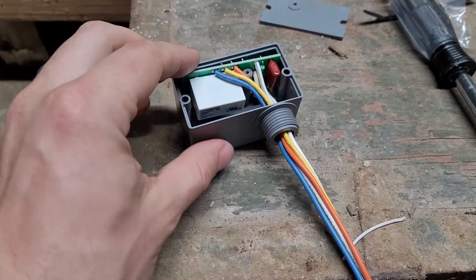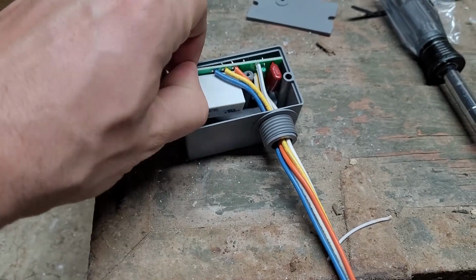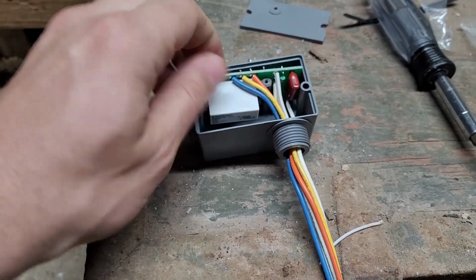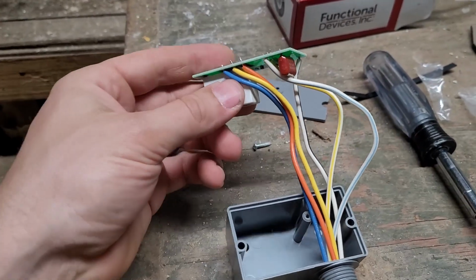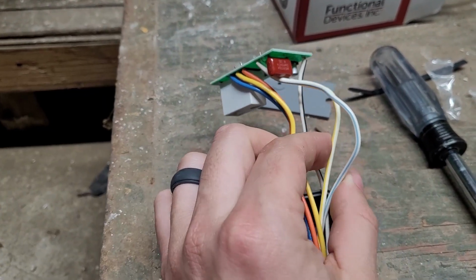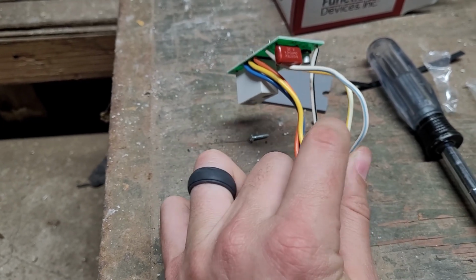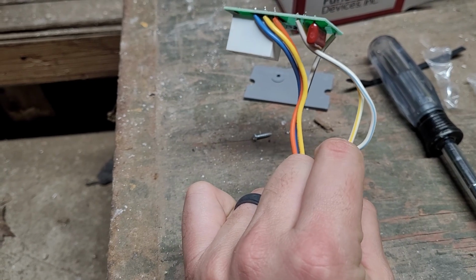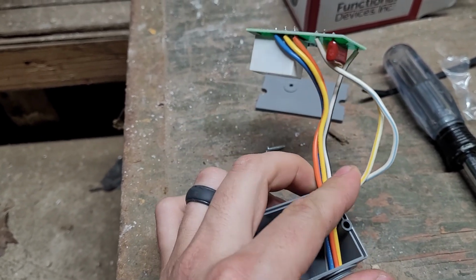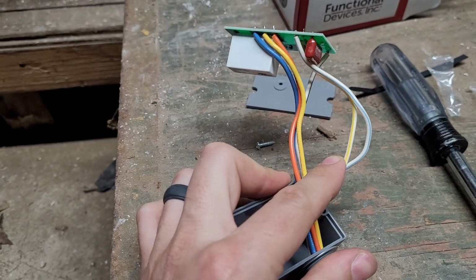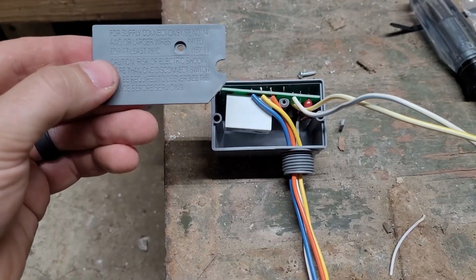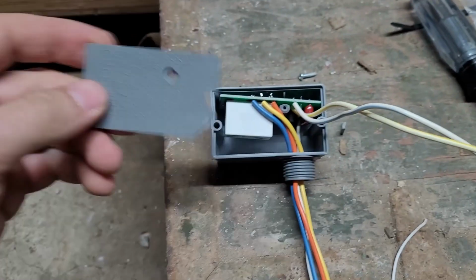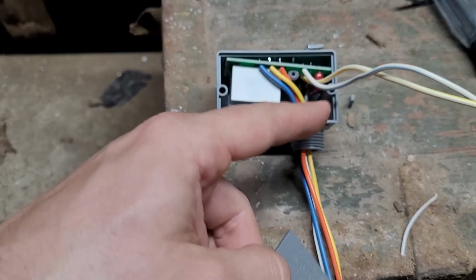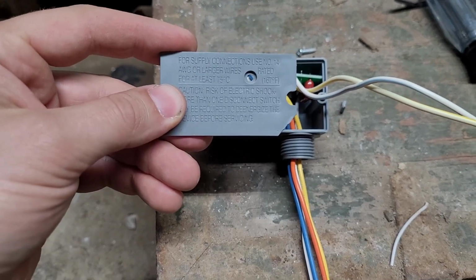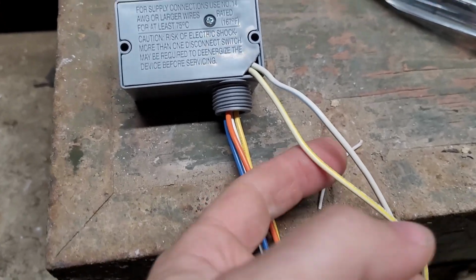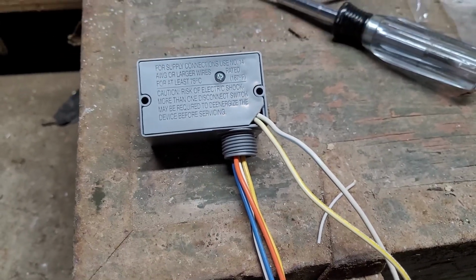So when you pop the back of the relay off, this little breadboard will slide out. You just have to push the wires up as you kind of tilt it and pull it out. Yeah, so you get the breadboard out, and then you're going to separate out the blue and yellow. And you just want to get some slack on the wires because you don't want to manhandle these connections right here. So just be gentle with it. So then you just stuff it back in there, and you've got your yellow and blue for your low voltage coil coming out. It's going to come out this corner, and so you just cut a corner off. So there it is, low voltage coming out the corner, and the high voltage stuff is all inside the enclosure.